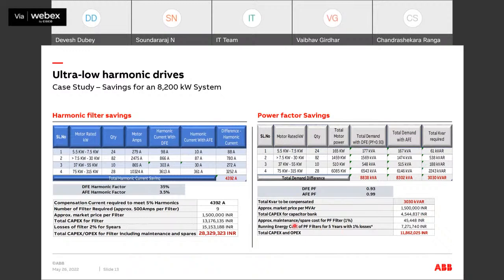Plus there will be approximate maintenance and spares for maintaining those filters. Plus if you calculate the running energy cost of these power factor compensation equipments, considering 1% of loss, it will be approximately 7 million. So that is also a huge cost coming across.